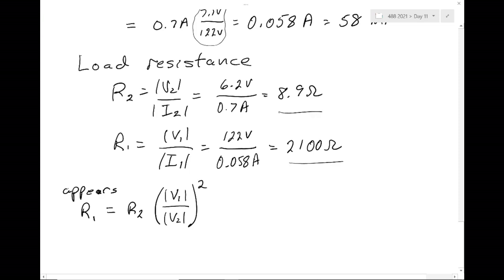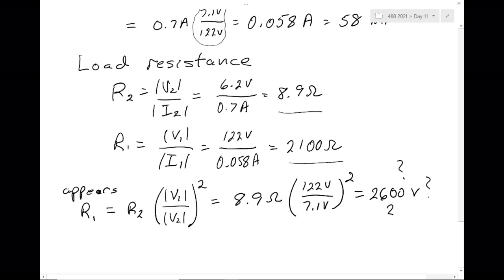If I actually do this calculation, it doesn't come out the same. I get 8.9 ohms times 122 volts over 7.1 volts squared. Make sure I have the turns ratio correct. That does not give me 2100. It gives me 2600. Why? Is what I've told you completely wrong? No. This is the ideal transformer equation. Our transformer is not ideal.